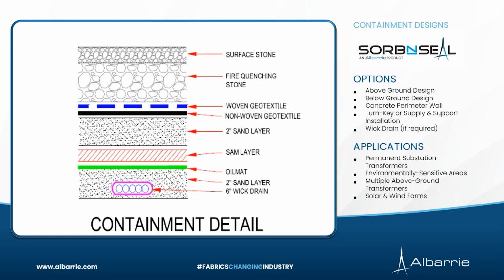Once we have this laid out, then we're going to fill the containment with the fire quenching stone, which is really just a fancy name for a clean washed stone between 1.5 to 3 inches in size, easily available anywhere in North America. Okay, so clean washed stone, 1.5 to 3 inches in size. The actual containment capacity is going to be calculated in the fire quenching stone. The materials themselves don't have any real significant ability to contain all of the oil you have in the equipment. Yes, they do absorb some, but it's not of great significance. So the actual containment capacity will be calculated in that fire quenching stone. That will determine how big, in terms of footprint and depth, the containment needs to be.